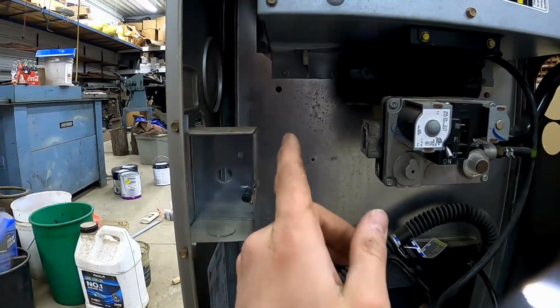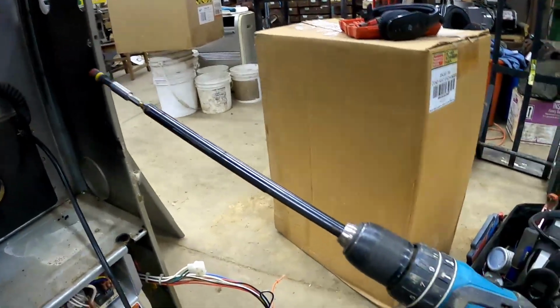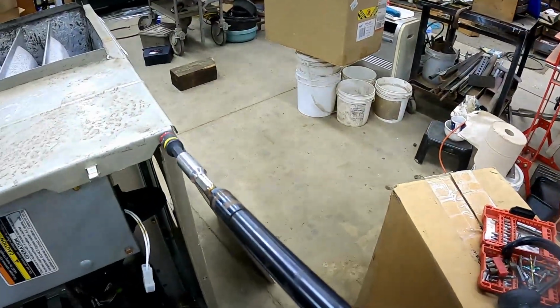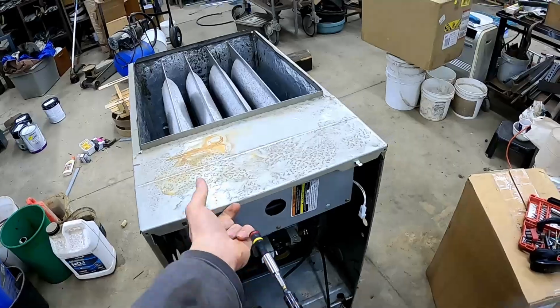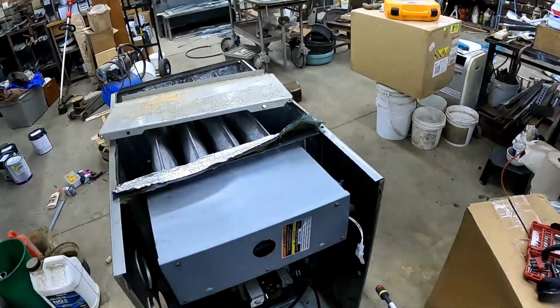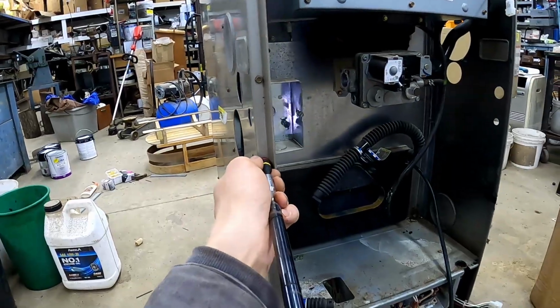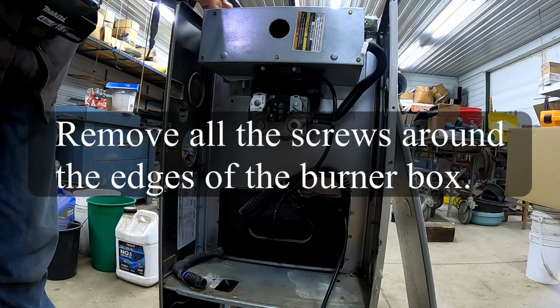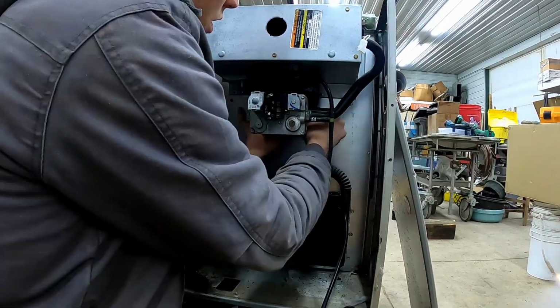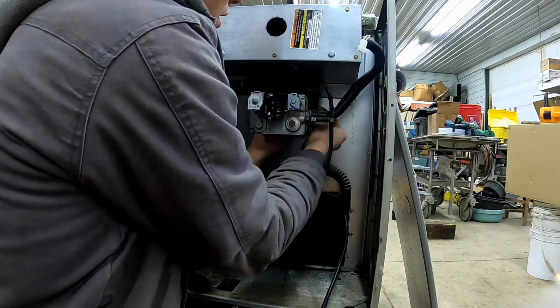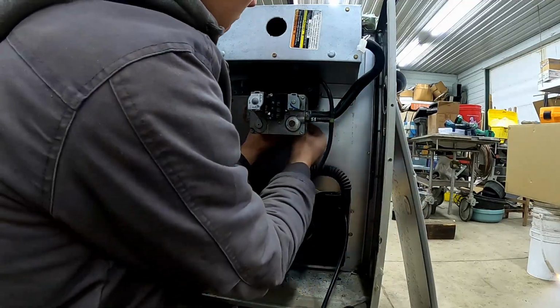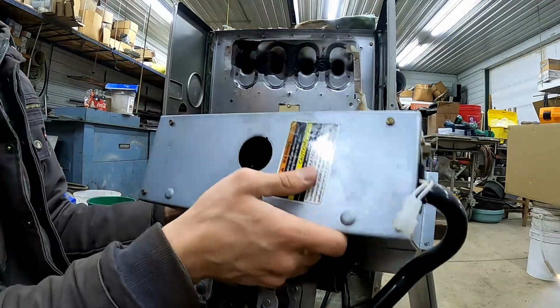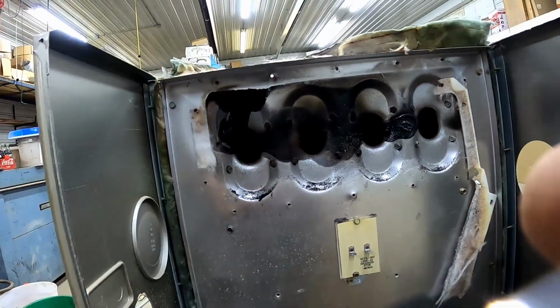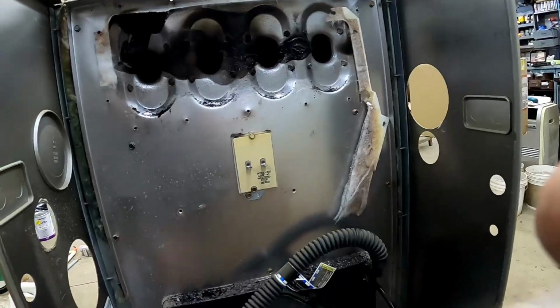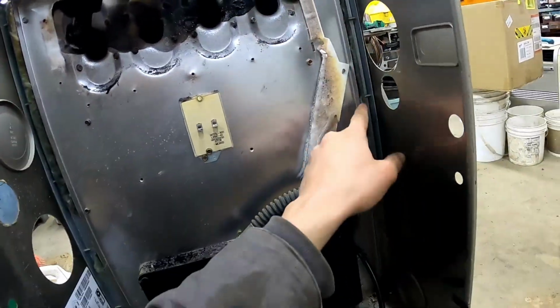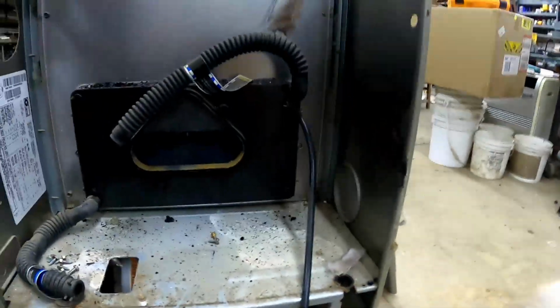Next we're going to remove the burner box, which means we have to take all those screws off. This is when it's nice to have an extension bit with your drill. Move our electrical box. And there is one screw up behind here that's kind of a bugger to get at. Just using a 1/4 inch to get at it. And there's the burner box. You can see that this thing was definitely burning poorly by the soot. So next we're going to remove the screws going up the sides and the 2 screws going up into the bottom.